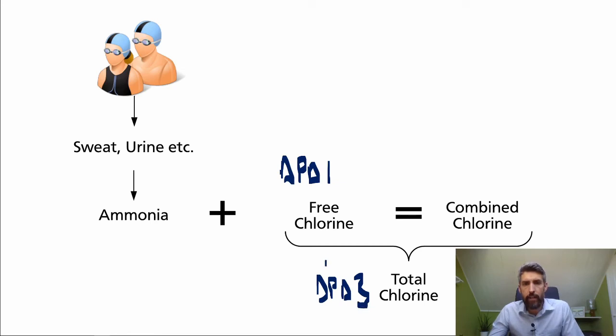It's the difference between the two that will tell you what the combined chlorine level is. So, for example, if we measured the free chlorine with a DPD-1 tablet and we got a reading of 1.5 for the free chlorine, and then we went on to test the total chlorine reading and we got a result of 2, then we'd be able to establish that there is a level of 0.5 of the combined chlorine. So the combined chlorine is the difference.